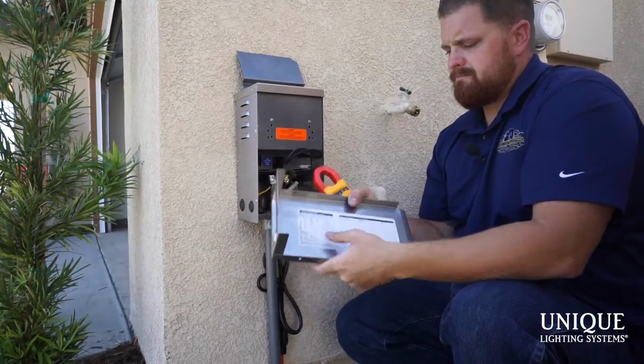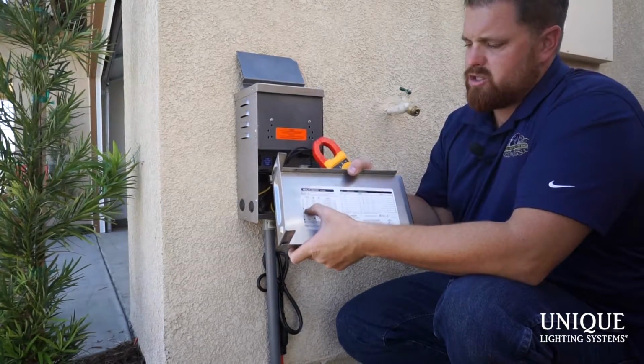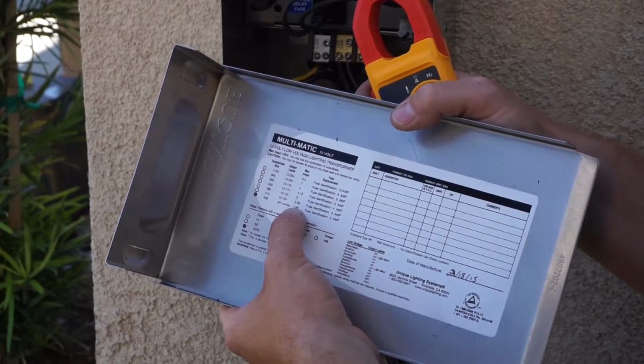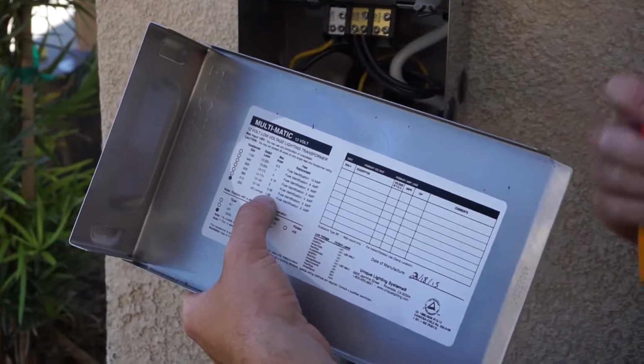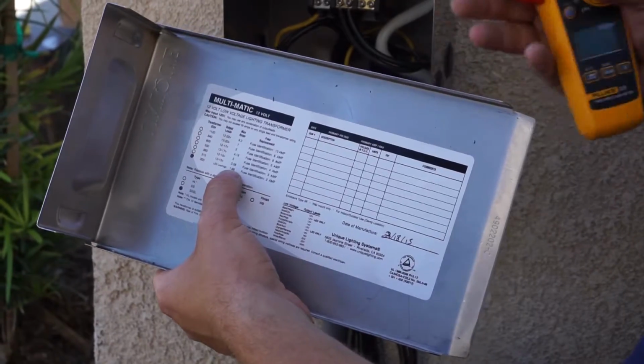Looking at the transformer, again, it's a 200 watt transformer. My maximum amperage I can put on this transformer is 16.6 amps. So if I exceed that 16.6 amps, I've got to make a change. I've got to go out there and reduce the wattage of the lamps. I've got to reduce the fixtures, whatever I have to do. But either way, no matter what, I have to be under 16.6 amps.